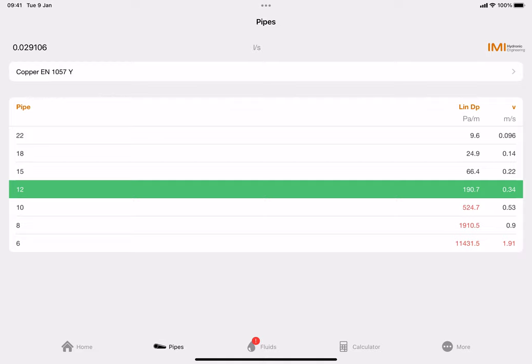This is a very big fallacy - a lot of people think you size pumps by the static height of a building. We did a poll the other day and about 24 percent of people still thought that - that is absolutely not the case. When you look at a 15-50 pump, the '15' stands for the bore size and the '50' stands for 50 KPA, or five meters of head - which is 50,000 pascals. So if we look at that 10 millimeter pipe drop at 524.7 pascals per meter, times six meters, you've got about 3,200 pascals, and yet we've got 50,000 to play with within that pump.